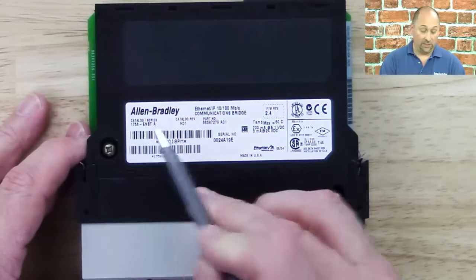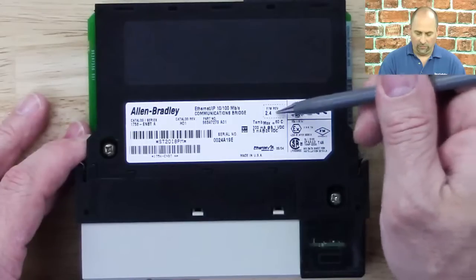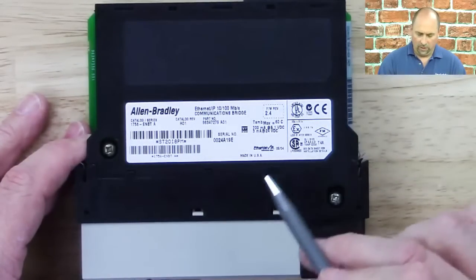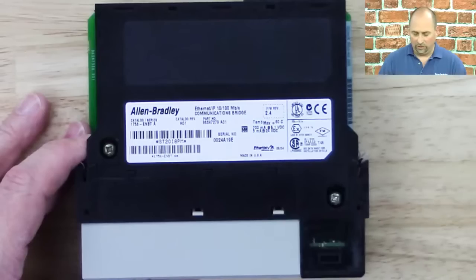And we can take a look here on the side at the label. We can see it's a 1756-ENBT, this is a Series A. We can see our barcode number, we can see the firmware it came from the factory at, and we can also see it's a 10/100 module. We can see when it was manufactured, and some other information as well.